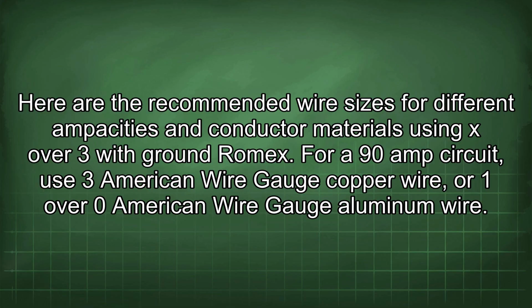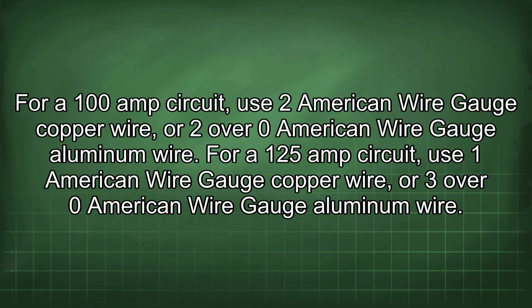Romex. For a 90 amp circuit, use 3 American wire gauge copper wire, or 1/0 American wire gauge aluminum wire. For a 100 amp circuit, use 2 American wire gauge copper wire, or 2/0 American wire gauge aluminum wire. For a 125 amp circuit, use 1 American wire gauge copper wire, or 3/0 American wire gauge aluminum wire.